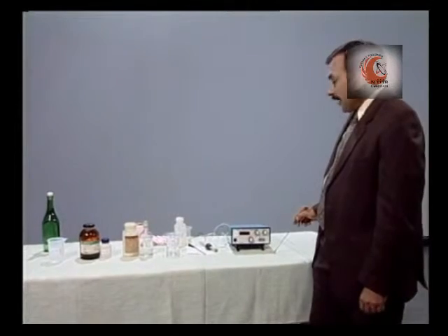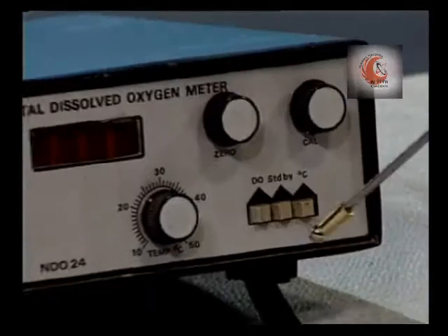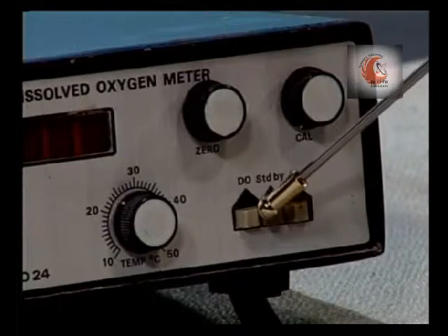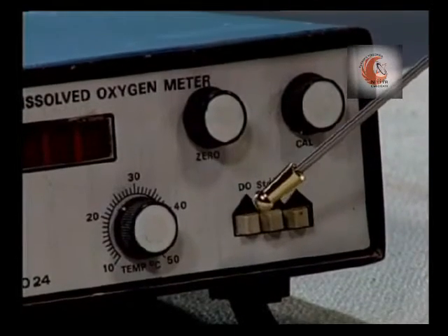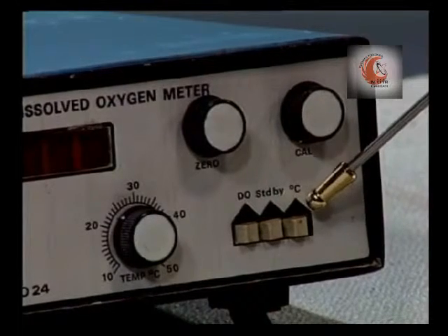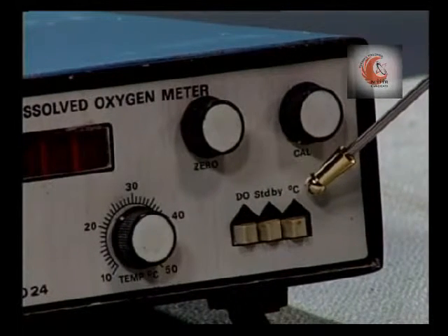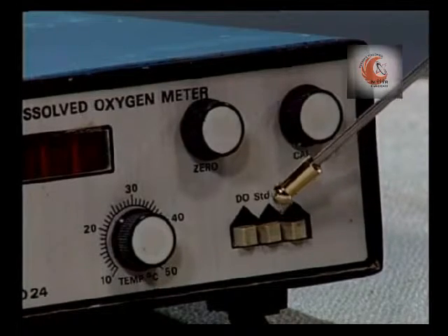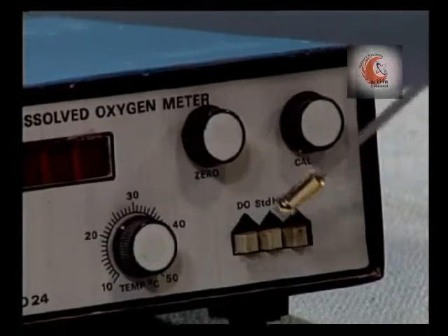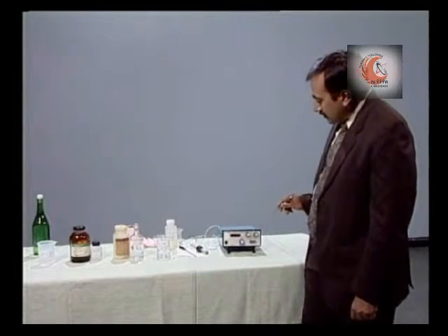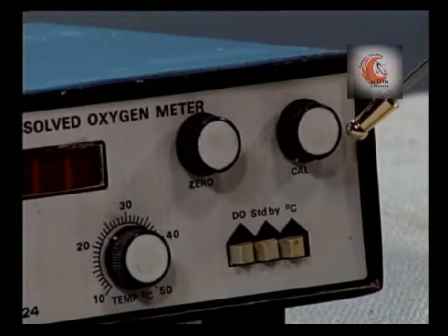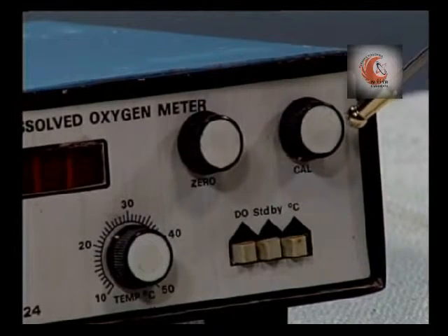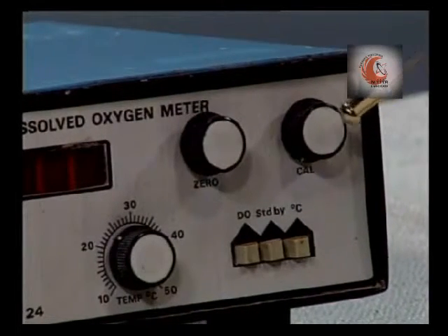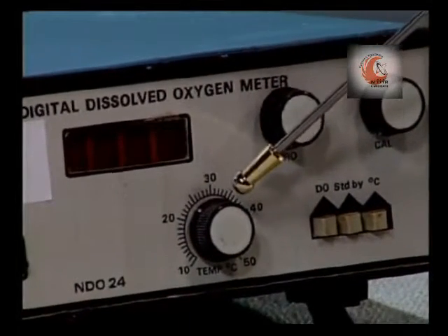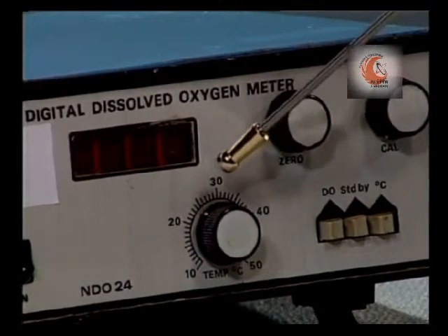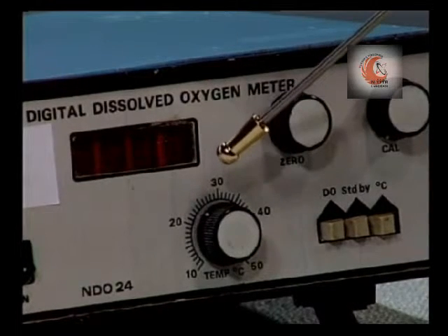The DO meter has a set of mode switches. DO switch to be used when measurement for DO are carried out, degree centigrade when temperature measurements are in progress, and standby when the instrument is not in use. 0 and cal knobs are to be used for calibration of the instrument. We have a temperature knob to set the instrument against the known temperature of the solution.